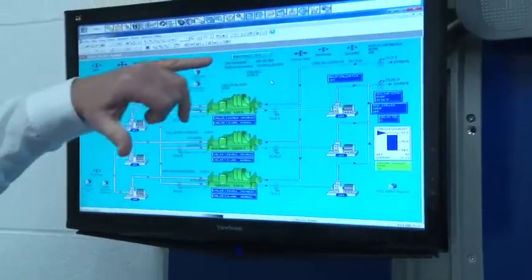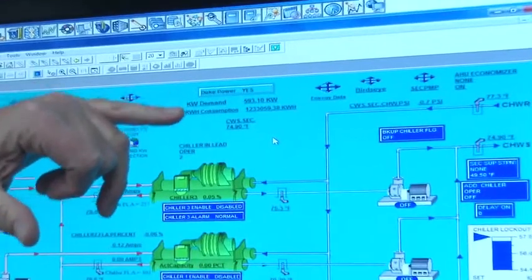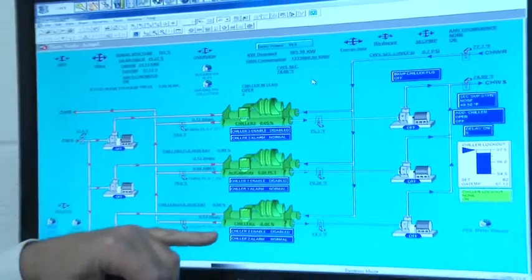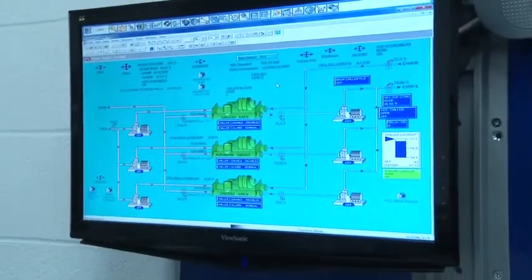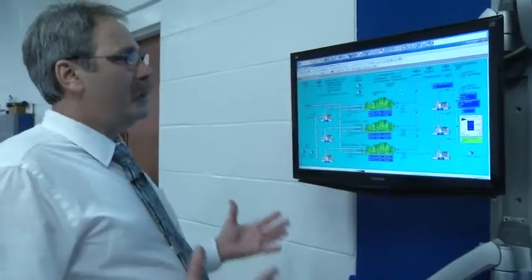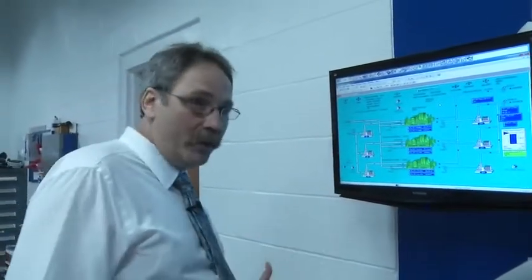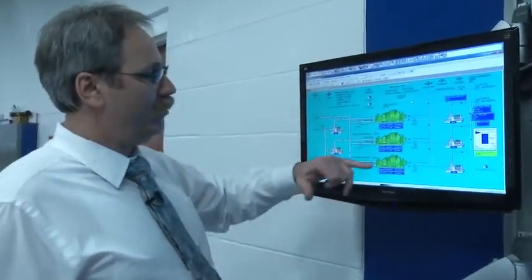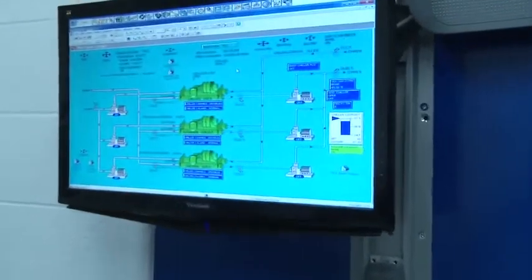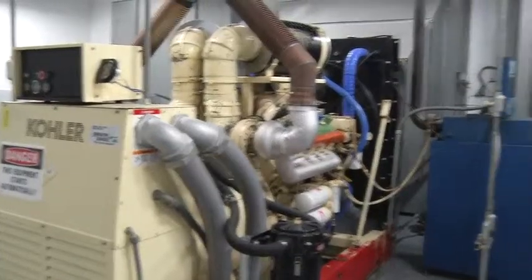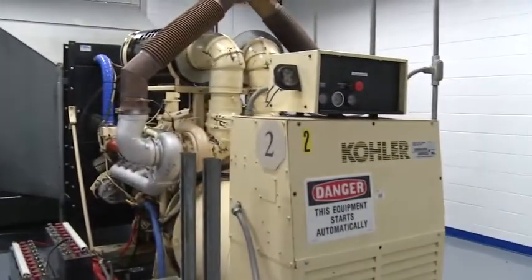One of the cool things about monitoring your outside power is when we lose power, we can have it send a signal to all the major pieces of equipment to shut down — give them a stop signal. So when the power comes back on and the generators come up, you're not slamming your system with every big piece of equipment at once and causing an equipment failure or a generator failure. Now we can individually choose which ones we want to start, so we can control how much load is on our generators. That's just another way of taking this system a little bit further.